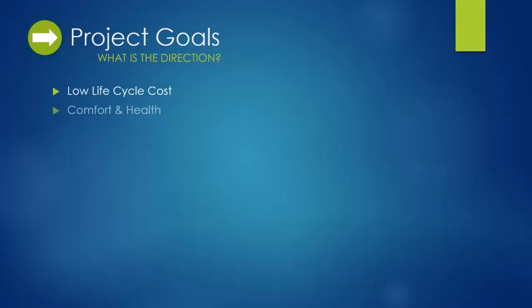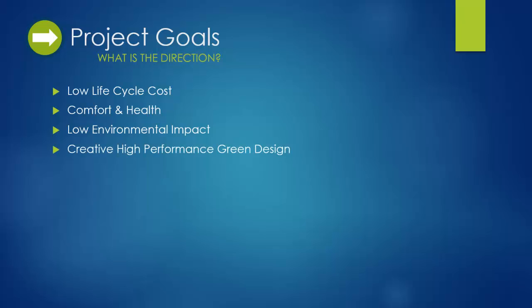Before selecting an HVAC system for this project, the following goals were considered. Low life cycle cost. This takes into account first cost and operational cost over a 50-year life. Comfort and health. This focuses on maintaining a high indoor environmental quality for the occupants. Low environmental impact. This tries to minimize water consumption, carbon footprint, and total use of refrigerant. Creative, high-performance green design. This incorporates creative ways to efficiently and comfortably condition the space. And synergy with architecture. This considers the effect the HVAC system will have on the aesthetics of the building and the spatial requirements needed for various systems.